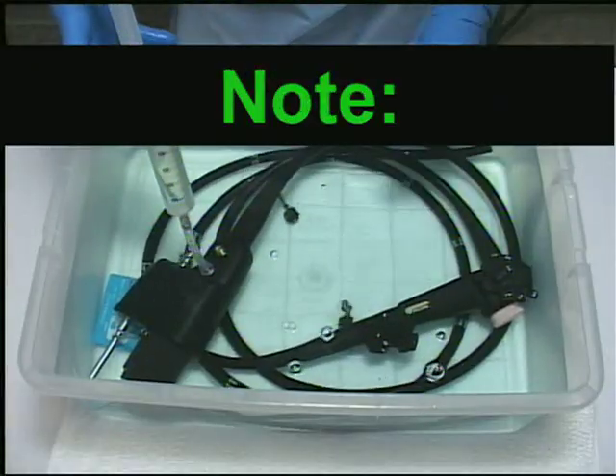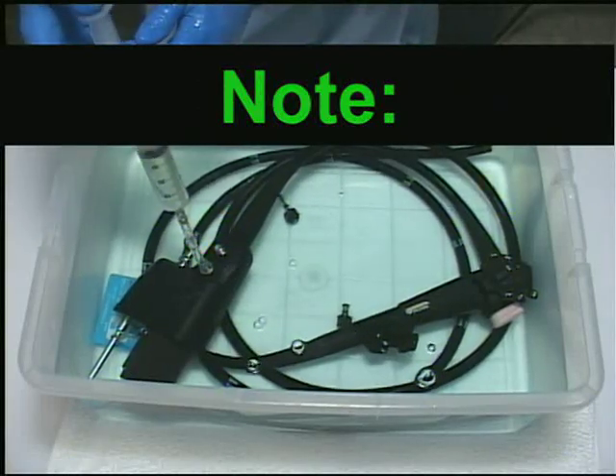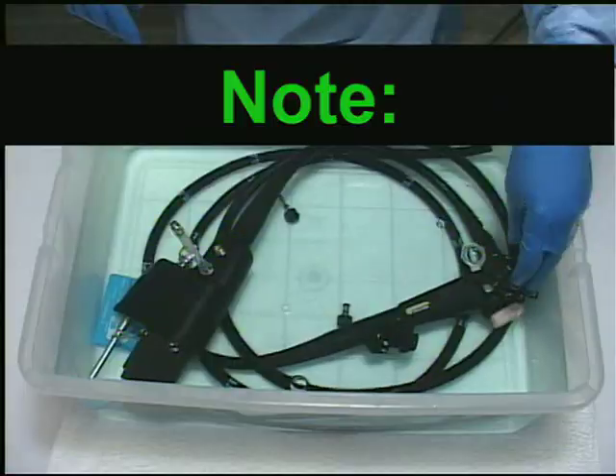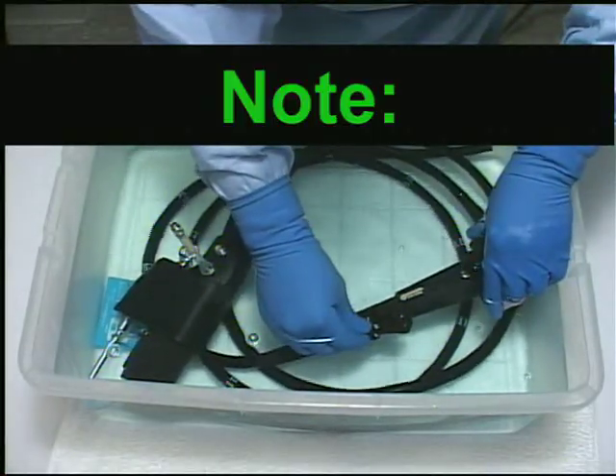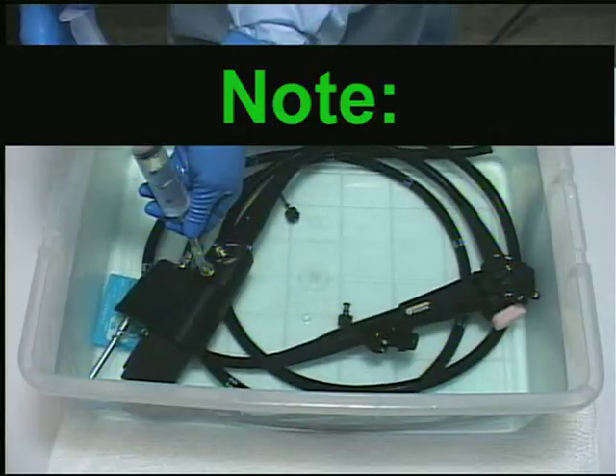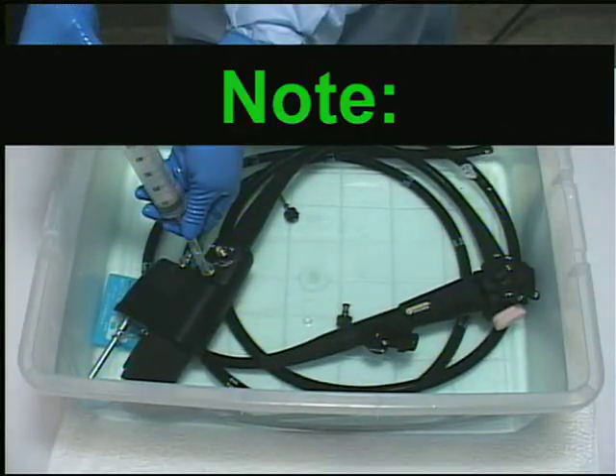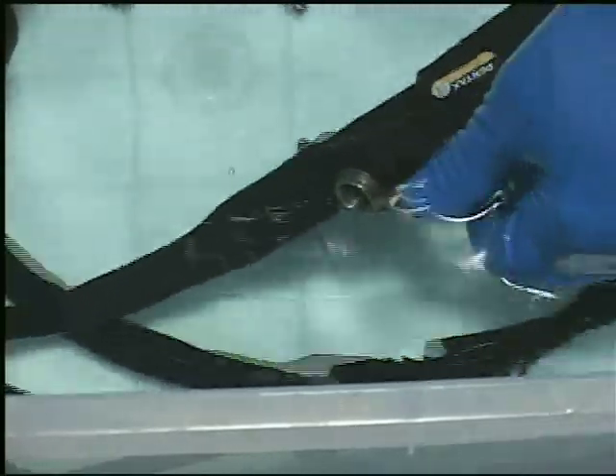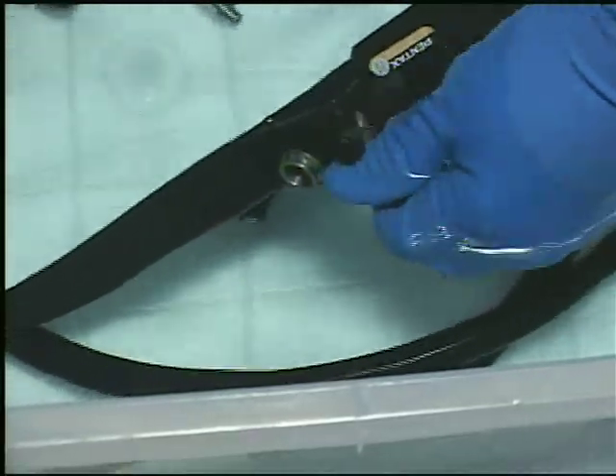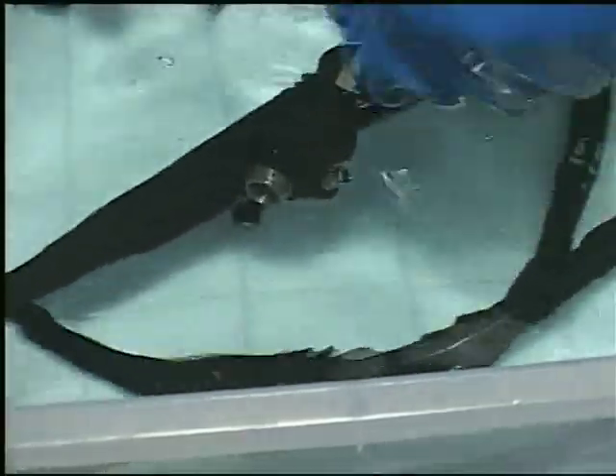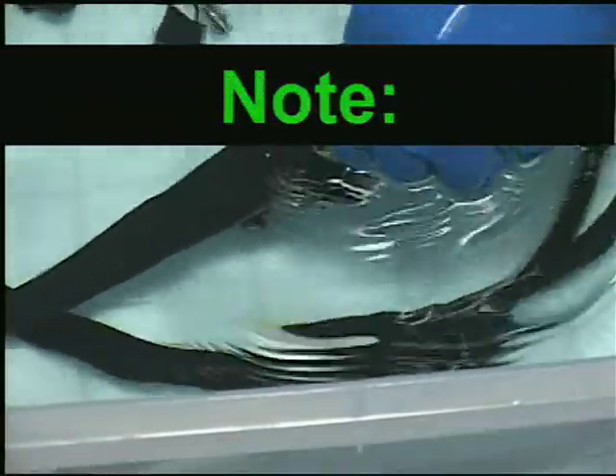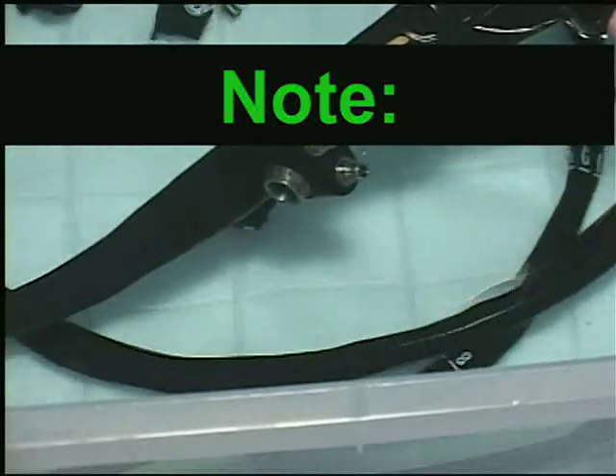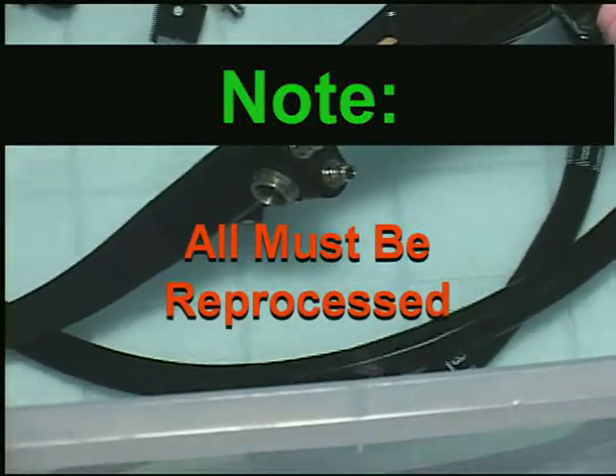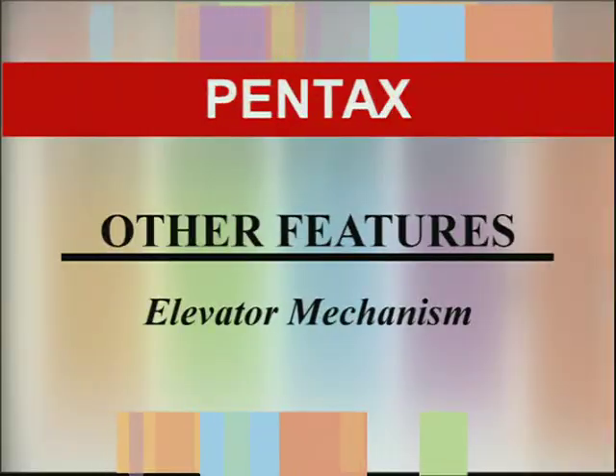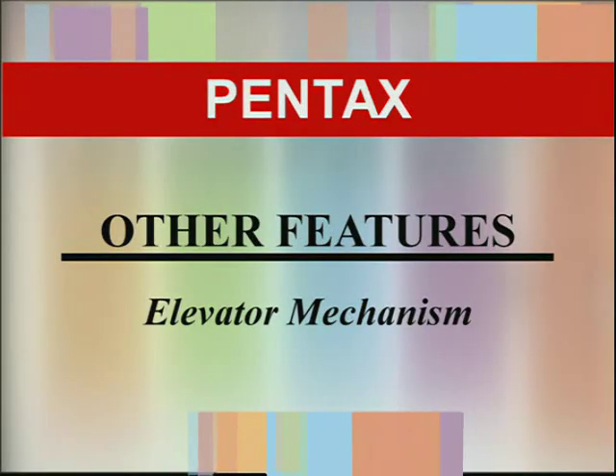Note: to ensure contact with all instrument suction channel surfaces, each channel should be flushed separately with detergent, disinfectant, and rinse water. Use the suction selector mechanism to alternately direct flow into each separate channel. Providing the entire endoscope remains immersed under solution, the suction selector mechanism should be removed and soaked separately in detergent and then in a disinfectant. Note: regardless of whether both channels and the suction selector mechanism are clinically used during a procedure, all must be reprocessed.